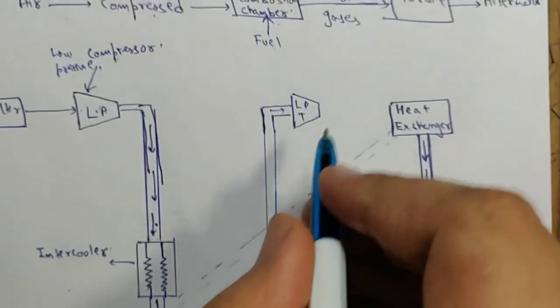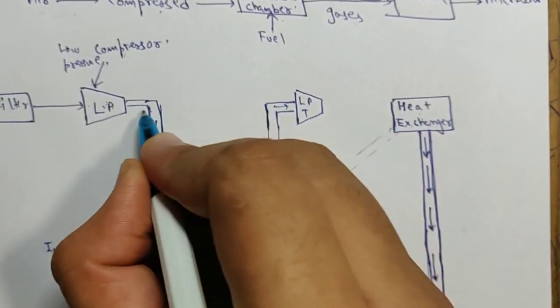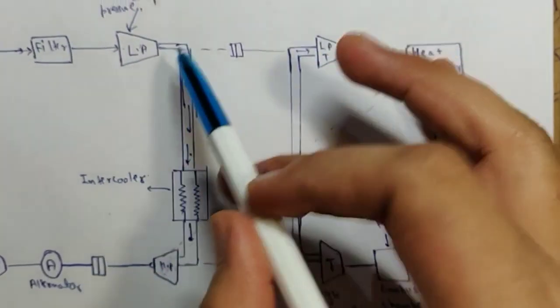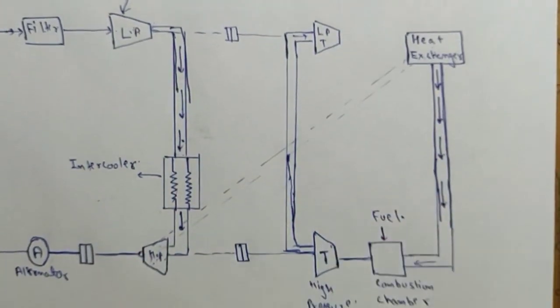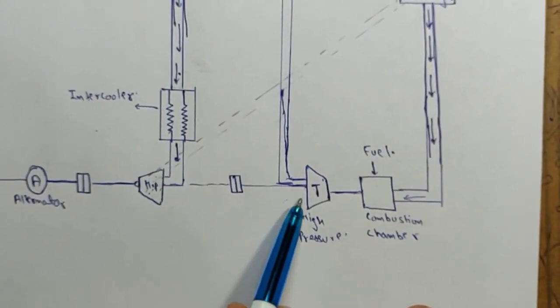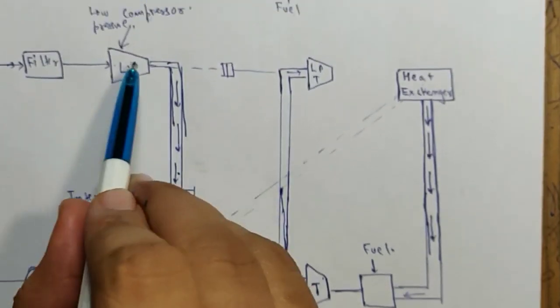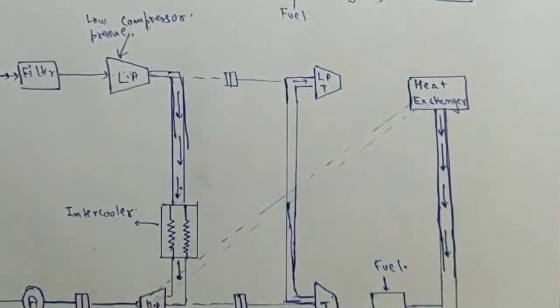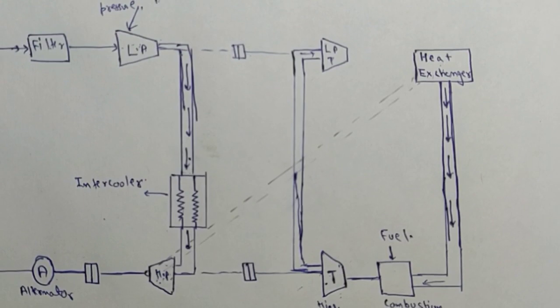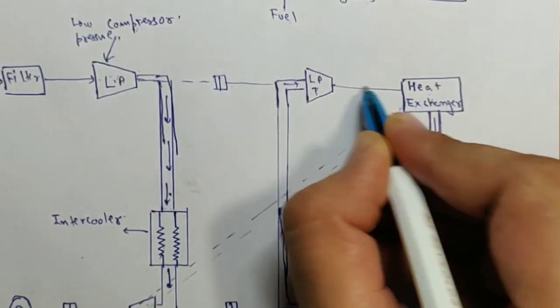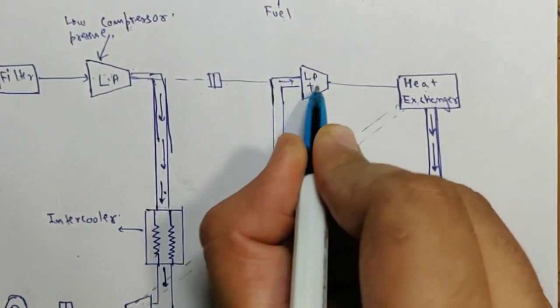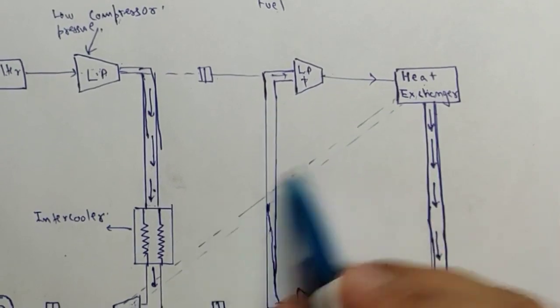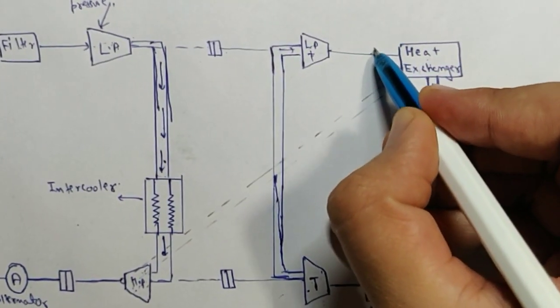This low pressure turbine is coupled with the low pressure compressor. Similarly, the high pressure compressor takes the energy of the high pressure turbine to run, and the low pressure compressor takes the energy of the low pressure turbine to run. They are both coupled with their respective turbines so that we don't require any external sources for the compressors to run. After the gas has expanded in the low pressure turbine, it is sent to the heat exchanger to utilize the remaining heat energy in the gas.